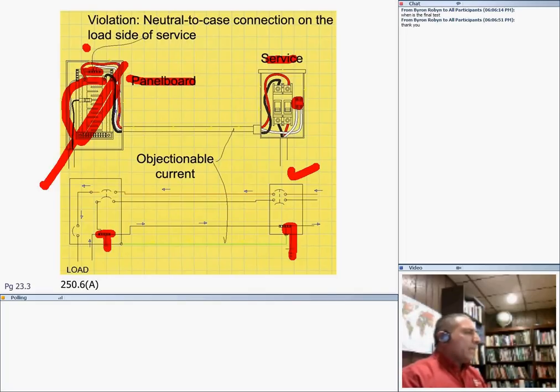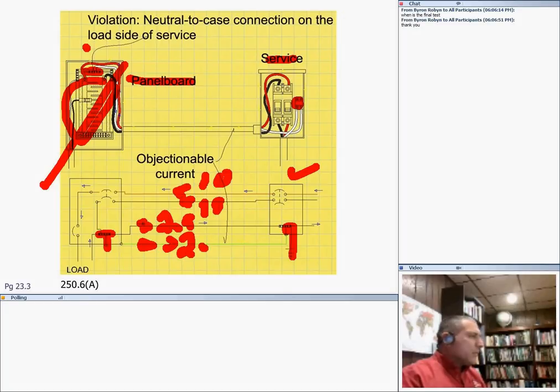And the reason why they don't bond again here, guys, if you bond twice, guess what? The neutral current will be going back. Joanne, my friend, if you bond twice, who cares, Chad? Why can't we bond twice? Well, let's look at this circuit. Suppose it's a multi-wire branch circuit. Say there's 10 amps here. There's also 15 amps in this one. The difference between them, guys, is 5 amps. Of the 5 amps, 2.5 is going to go through the neutral, and 2.5 is going to go through the ground.